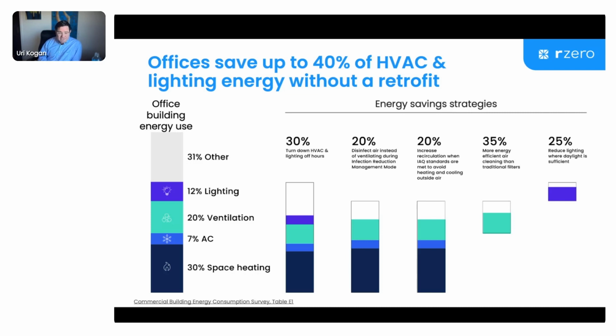So the existing ASHRAE standards for ventilation that are embedded in building codes and sustainable building programs like LEED, they offer several different approaches to figuring out how much ventilation you need. The most common is based on occupancy, and usually people use that to calculate the size and scope of their system when they build the building, and they never come back and adjust it dynamically, which is what we talked about in the first strategy.